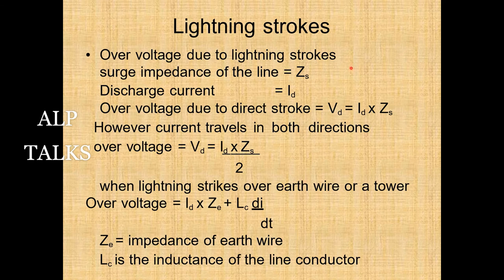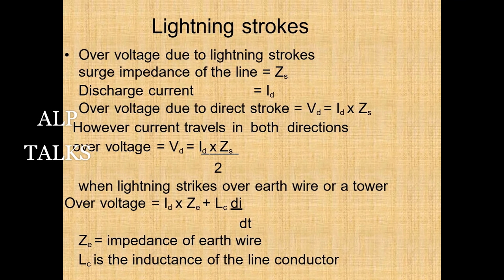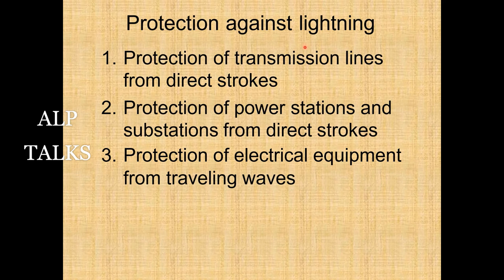Static-induced charges also accumulate on overhead conductors when a charged cloud passes above. When the cloud is swept away, the charge is released and travels in both directions as two traveling waves; the earth wire does not prevent such surges. For overvoltage due to lightning stroke: surge impedance of line is Zs, discharge current is Id, and overvoltage is Id × Zs (taking half for each direction). When lightning strikes at a tower, the overvoltage includes L·di/dt, where Ze is the impedance of the earth wire and Lc is the inductance of the line conductor.